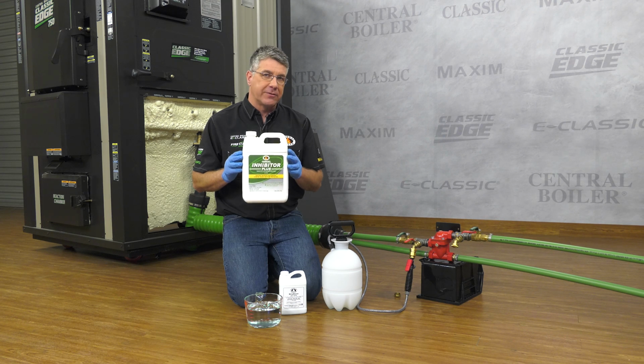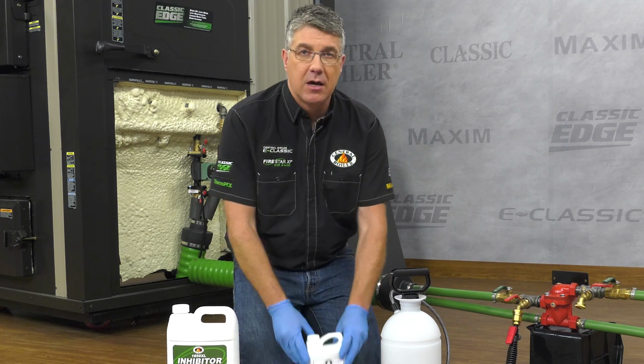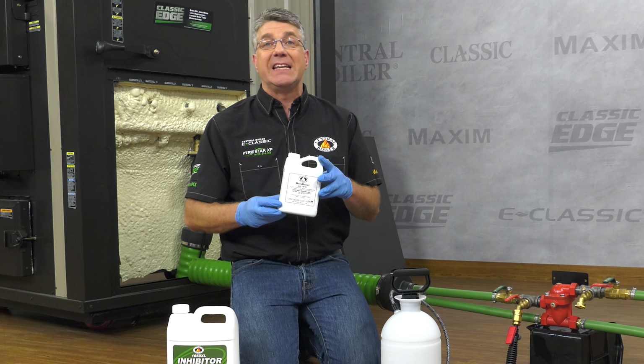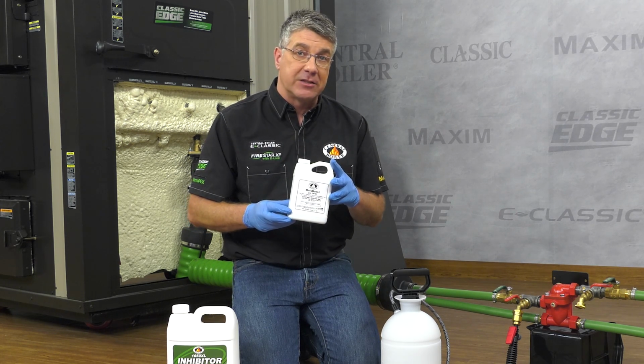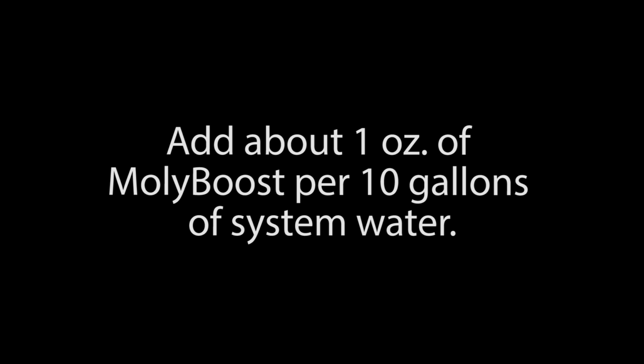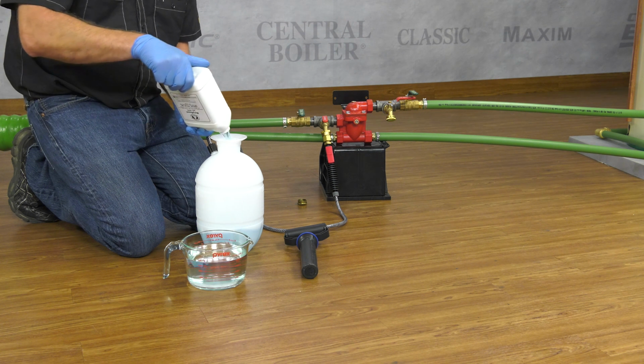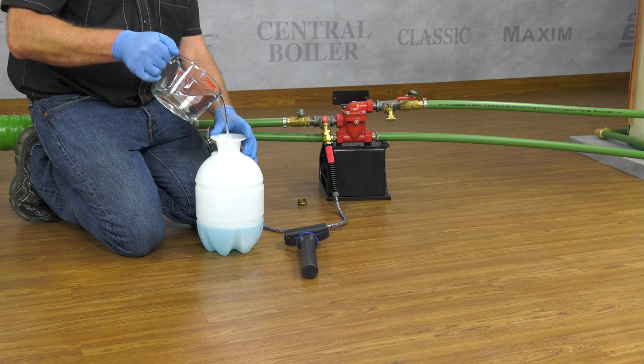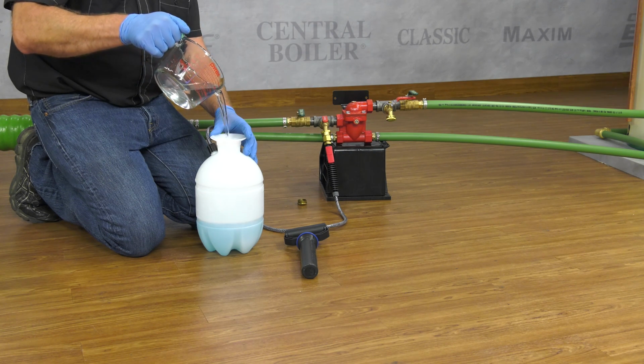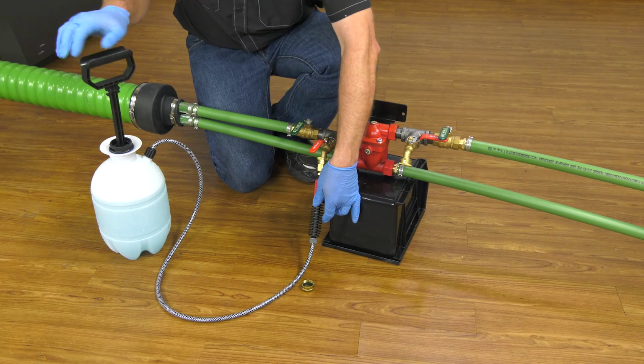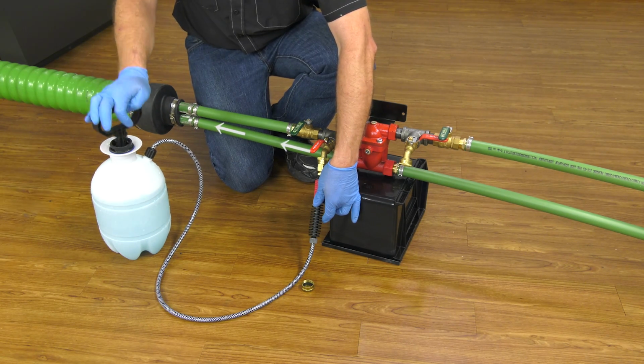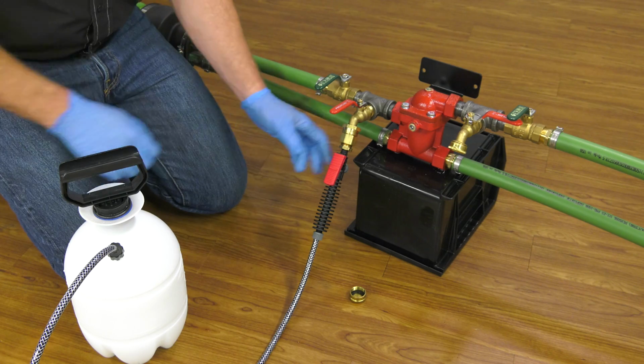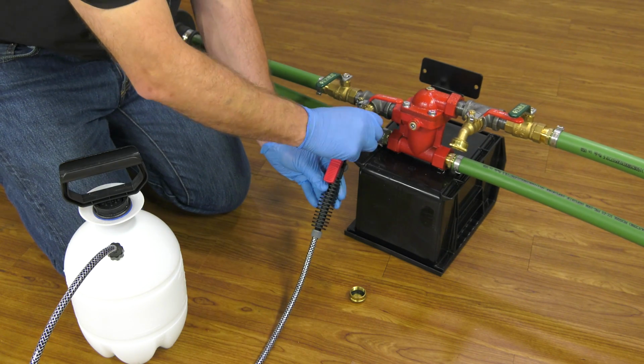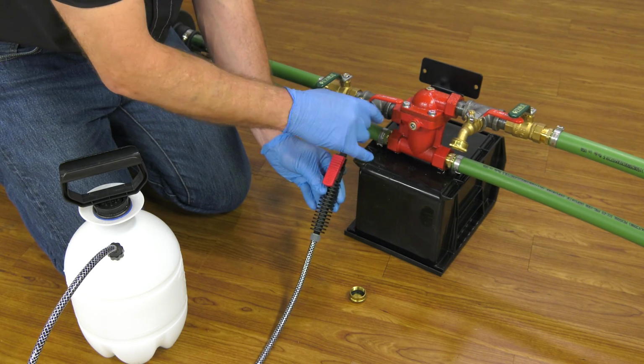The nitrites in Corrosion Inhibitor Plus help protect the metal in your furnace from corrosion. MolyBoost helps the corrosion inhibitor work even better by keeping these nitrites in balance. Add about 1 ounce of MolyBoost for 10 gallons of system water. For our Classic Edge 750, we'll add 1 quart of MolyBoost. Add a little water in the pump jug with the MolyBoost to help it mix better in the furnace. We repeat the process to add the MolyBoost to the outdoor furnace through the return line. Once the correct amount of MolyBoost has been added to the system, close the valve and remove the pump jug.